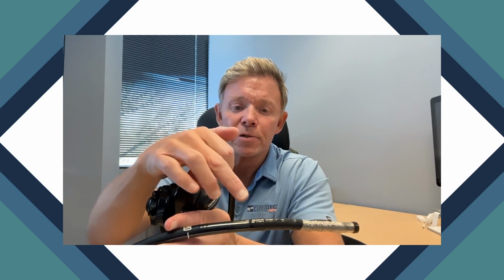What happens is that both of these adhesive seals, over time, just from the routine cleaning of the scope, the chemicals that the scope is subjected to during the cleaning process, and just the manipulation of the tube and the distal tip, those adhesives will break down. And they break down in a series of progression. The first thing that usually happens, from the chemical solutions, is they'll start to turn gray. They'll start to look discolored.